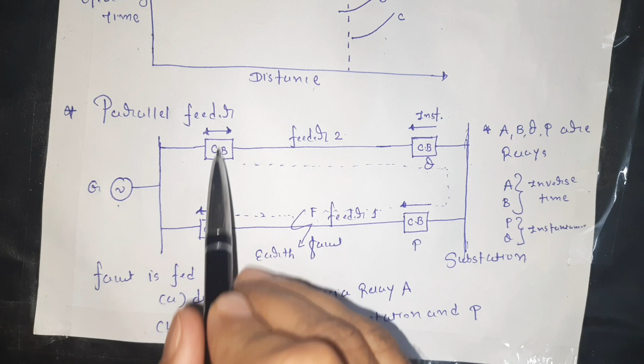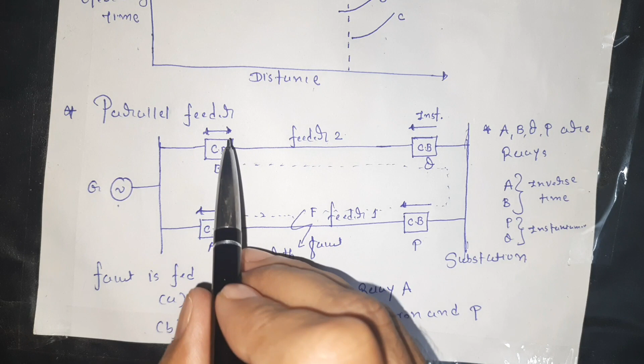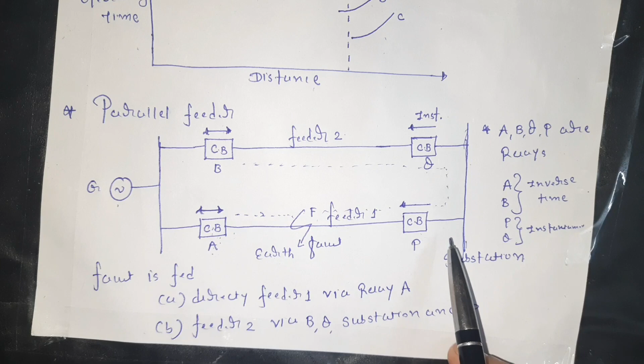As far as the characteristics are concerned, the generating station side relays are having inverse time characteristics. So A and B have the inverse time characteristics. And P and Q, which are nearer to the substation, have the instantaneous type characteristics, and they will operate only when the power flows in the reverse direction. Then and then these two relays will operate, right?